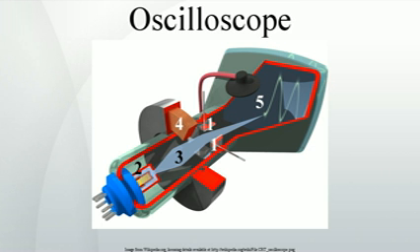Dual and multiple trace oscilloscopes. Oscilloscopes with two vertical inputs, referred to as dual trace oscilloscopes, are extremely useful and commonplace. Using a single beam CRT, they multiplex the inputs, usually switching between them fast enough to display two traces apparently at once. Less common are oscilloscopes with more traces. Four inputs are common among these, but a few, Kikusui for one, offered a display of the sweep trigger signal if desired. Some multi-trace oscilloscopes use the external trigger input as an optional vertical input, and some have third and fourth channels with only minimal controls.